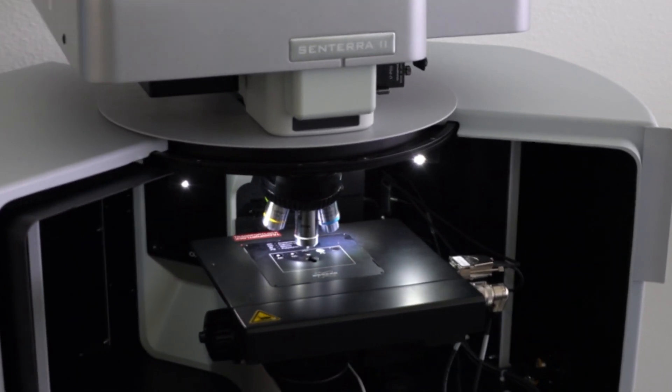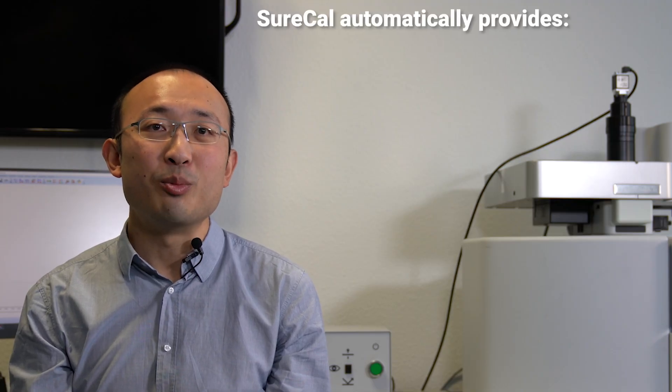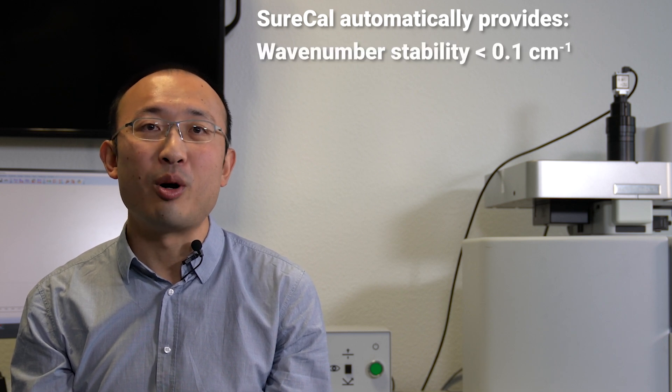Simply put, a Senterra II must never be manually calibrated. It does it completely automatically with the high wavenumber stability of 0.1 wavenumber.